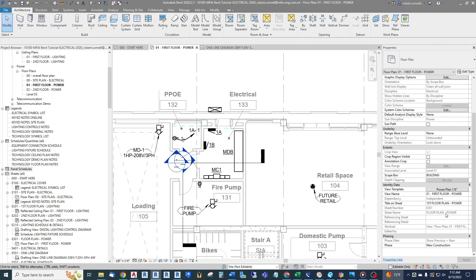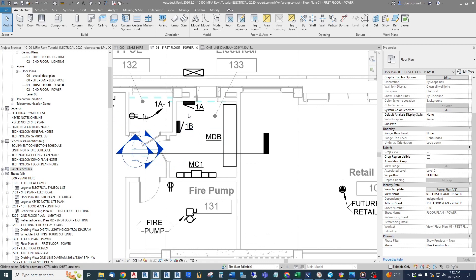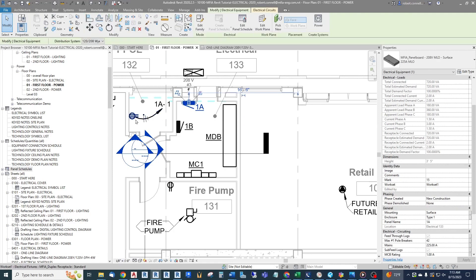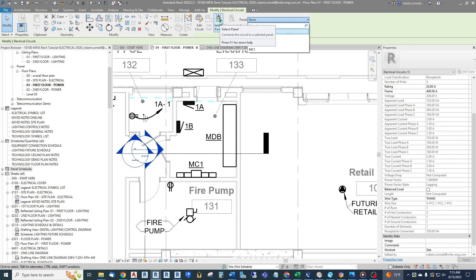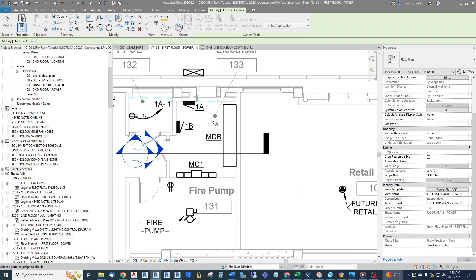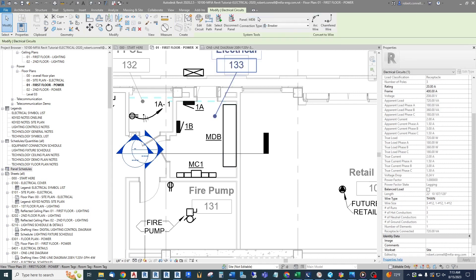Let's get started connecting panel 1A to our main distribution board. Click on panel 1A — it's similar to how we circuited receptacles. Find the power button up under Create Systems. Click the power button and we get a similar dropdown giving a list of all other equipment of the same voltage rating that we can connect to. We could actually connect panel 1A to panel 1B, to the main, or to the meter center. We can also go to Select Panel and select the panel with our cursor. Let's connect to MDB — it says we're connecting to panel MDB as a circuit breaker.